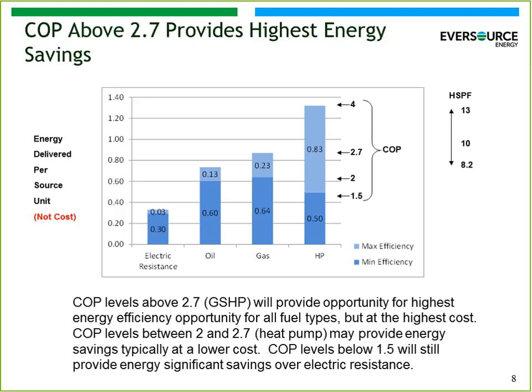As we move across, you look at oil, and we plotted these using a higher and lower efficiency, because oil furnaces might range in efficiency from the low 70s to the high 80s. So we tried to account for that range. Two things are happening: the oil boiler or furnace isn't going to be 100% efficient, and for each gallon of oil there's about another 15% adder that accounts for the energy it took to extract that oil from the ground and deliver it to your home. So from a source BTU basis, oil is much better than electric resistance, but it's still not close to 100%.